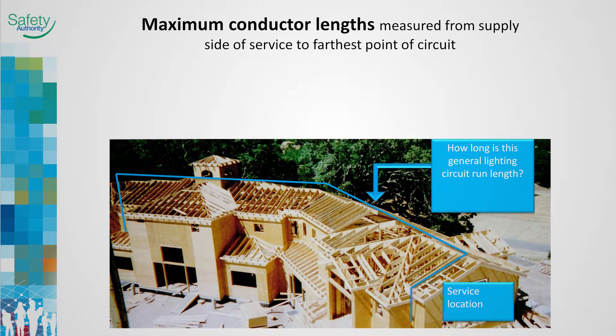The Appendix B note for Rule 8102 Sub Rule 3 indicates that the voltage drop of lighting and general use branched circuits in dwelling units will meet the requirements of 8102 Sub Rule 1 when the conductor length from the supply side of the consumer service to the furthest point of utilization is less than or equal to the values shown in Table 68. Table 68 limits the length of a 15-amp branched circuit with number 14 conductors to 38 metres. The length of the same 15-amp branched circuit would be increased to 60 metres if number 12 conductors were used. Providing a home run that is one size larger will help reduce the voltage drop considerably.